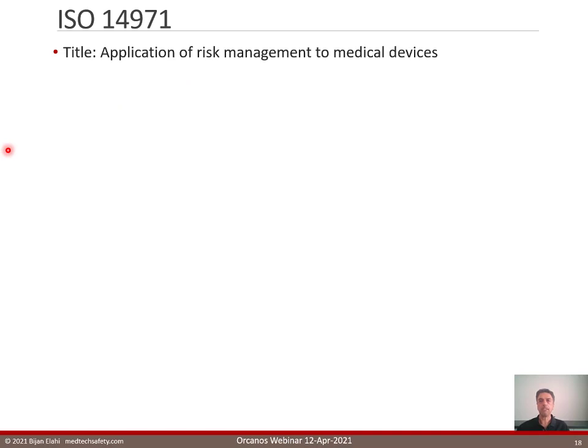The title of the standard ISO 14971 is Application of Risk Management to Medical Devices. Before ISO 14971, there was no standard for medical device risk management. It was originally developed in 1998 with participation of delegates from 112 countries. ISO Technical Committee 210 Working Group 4 was formed to produce ISO 14971.